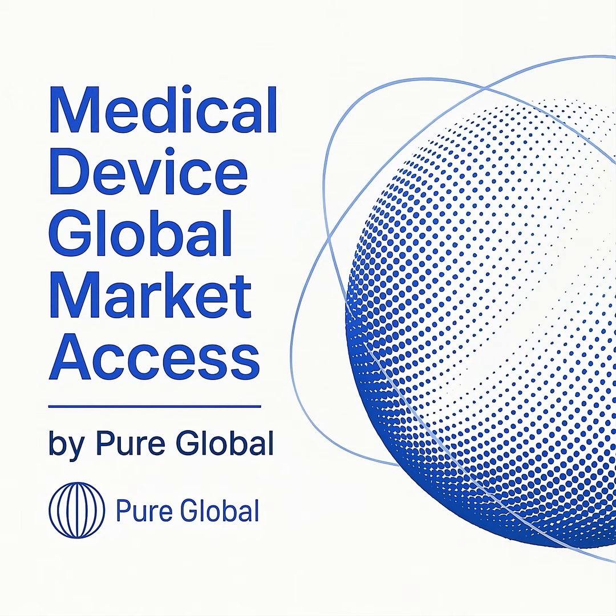To balance this newfound flexibility, the FDA has established a set of special controls that manufacturers must adhere to. These are mandatory requirements that provide a reasonable assurance of the device's safety and effectiveness. The special controls include several key areas. First, comprehensive software verification, validation, and hazard analysis must be performed. Second, the PCCP itself has stringent content requirements, including a clear description of the scope of permitted modifications and robust protocols for change validation. Third, labeling must be incredibly detailed. It needs to include a summary of the algorithm's performance data, its limitations, the type of data it was trained and tested on, and clear instructions for use. Finally, manufacturers must implement robust cybersecurity measures to ensure device integrity and protect patient data.